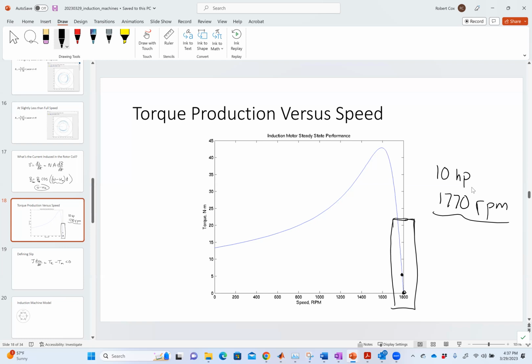So how long does an induction motor last? Basically forever, because the thing that wears out on any motor is the bearings. On a synchronous machine, I have to somehow get current into a rotating piece — that's not easy. I need something called a slip ring to force it in, which means a rotating and a stationary device touching each other, and that wears out after a while. The beauty of the induction machine is there's no touching — I'm just inducing the current in that thing.